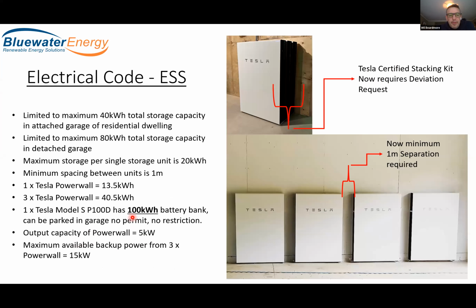Electrical code with respect to batteries: we're limited to 40 kilowatt hours total storage capacity in the home now. The code changed May 5th this year, and it says we're no longer able to put batteries in residential dwelling units. That includes all areas of the home, even unoccupied areas such as a furnace room. We are able to put batteries in an attached garage, but the limit is 40 kilowatt hours total storage capacity in an attached garage.